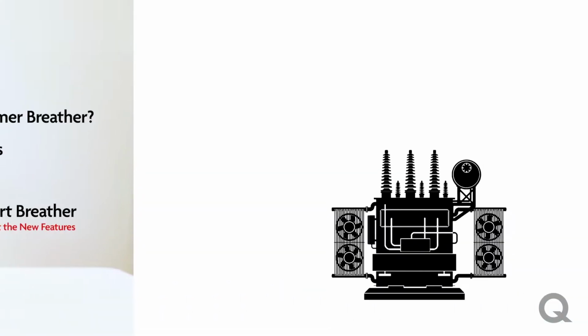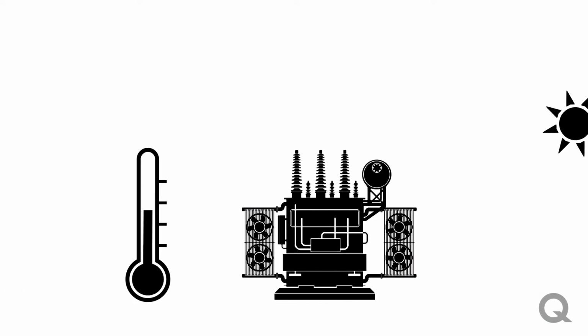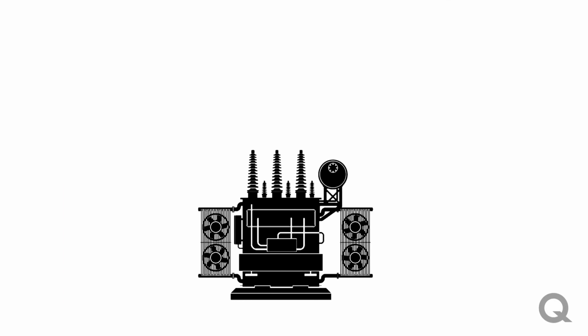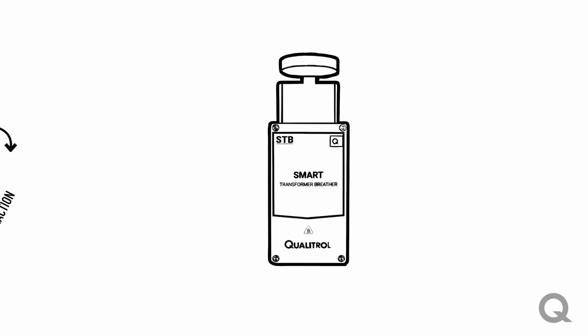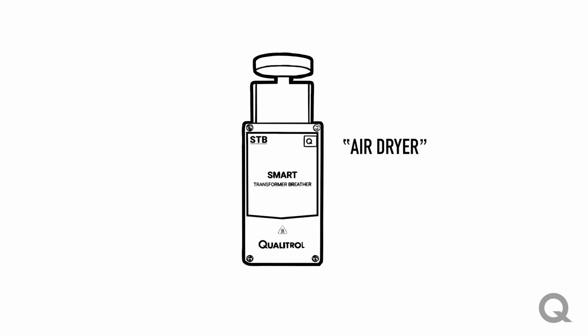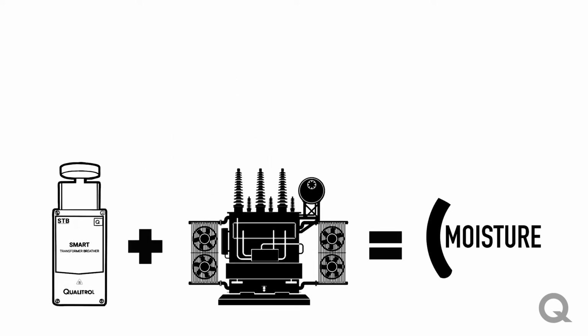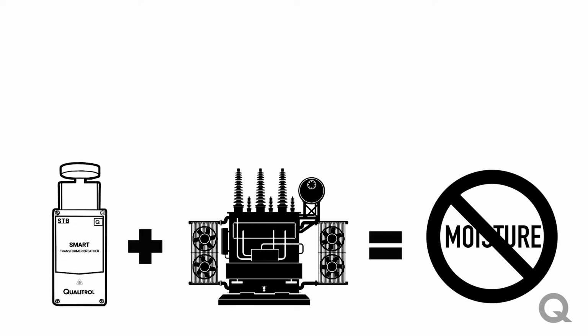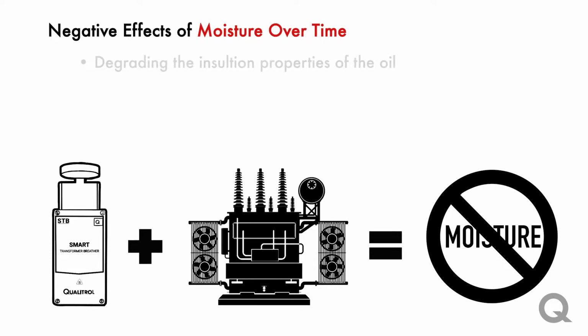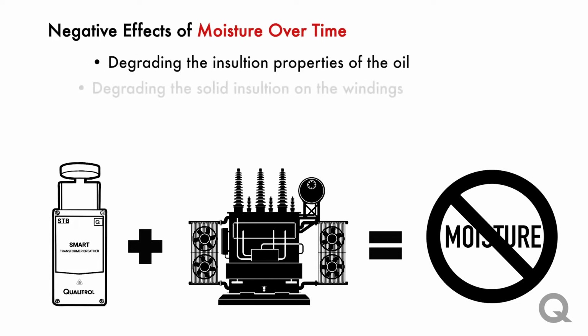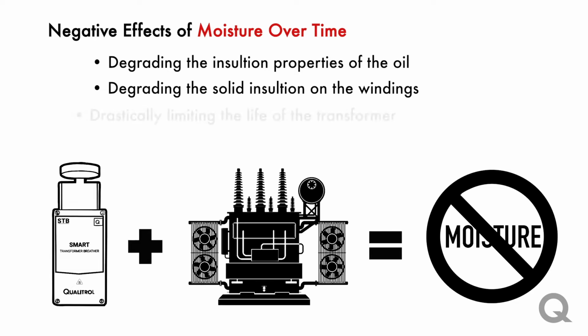So in a conservator style transformer, as the insulating oil heats and cools due to loading or ambient conditions, that oil also expands and contracts, causing a breathing function of the transformer. A breather or air dryer is needed to prevent moist air from entering the transformer and saturating the oil. Over time, the accumulation of this moisture in the transformer will negatively affect the overall life of the asset. The moisture can degrade the insulation properties of the oil, as well as the solid insulation on the windings, and this will limit the life of a transformer drastically over time.